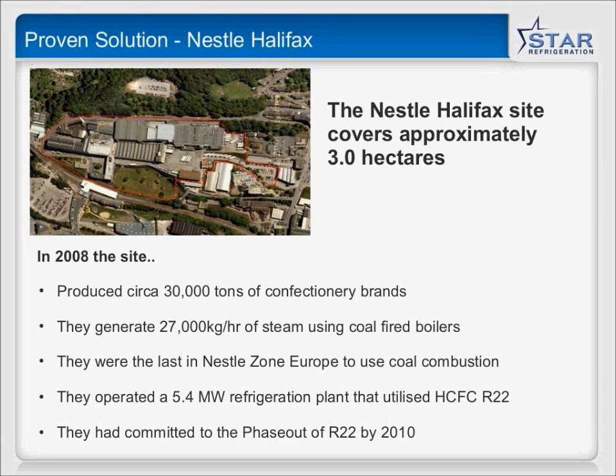It really was pretty grim. It was the last Nestle site in Europe to be burning coal to make steam. We had a fantastic realization during the project that their boilers were something like 80% efficient, but the steam distribution system was only about 60% efficient. So they were actually only getting 50% of the chemical energy from the lump of coal into the process.